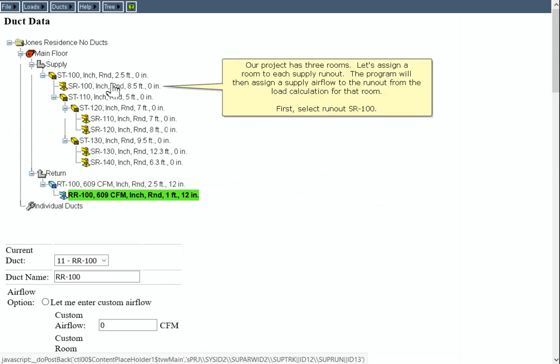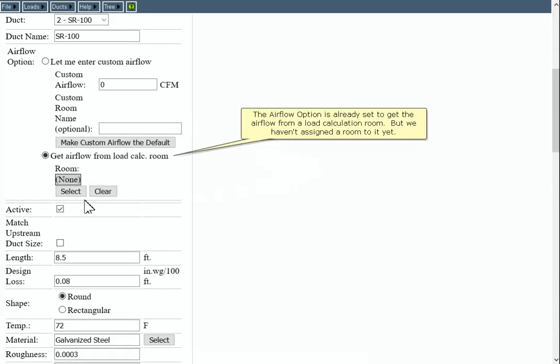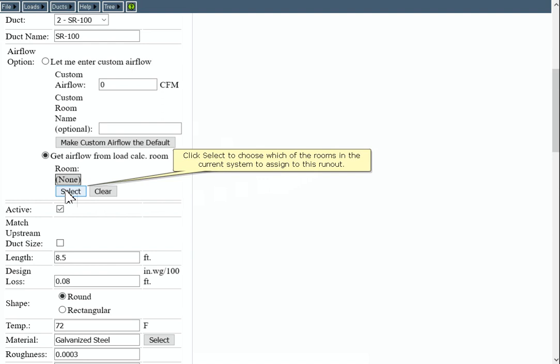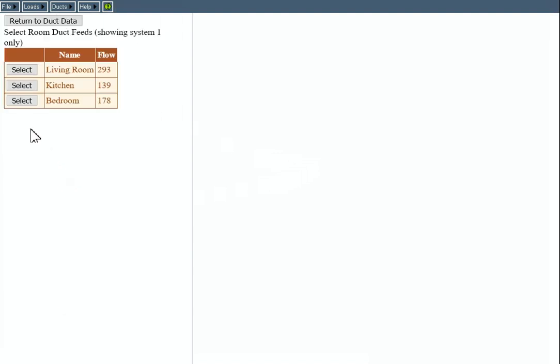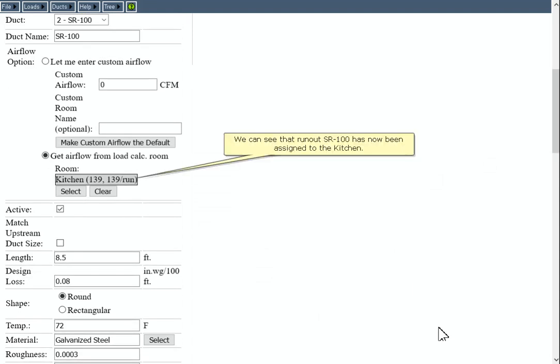Our project has three rooms. Let's assign a room to each supply runout. The program will then assign a supply airflow to the runout from the load calculation for that room. Select Runout SR100. The Airflow option is already set to get the airflow from a load calculation room, but we haven't assigned a room to it yet. Click Select to choose which room to assign to this runout. Runout SR100 feeds the kitchen, so click the Select button for that room. We can see that runout SR100 has now been assigned to the kitchen.